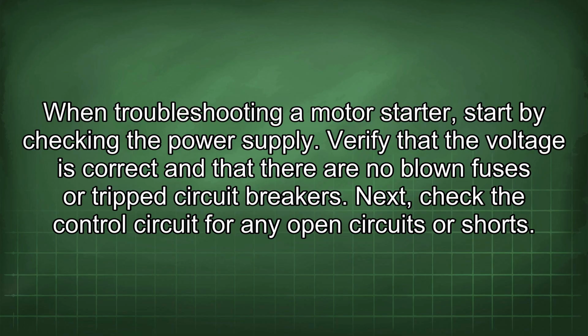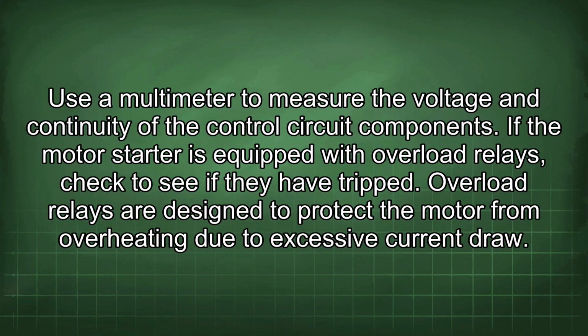When troubleshooting a motor starter, start by checking the power supply. Verify that the voltage is correct and that there are no blown fuses or tripped circuit breakers. Next, check the control circuit for any open circuits or shorts. Use a multimeter to measure the voltage and continuity of the control circuit components.